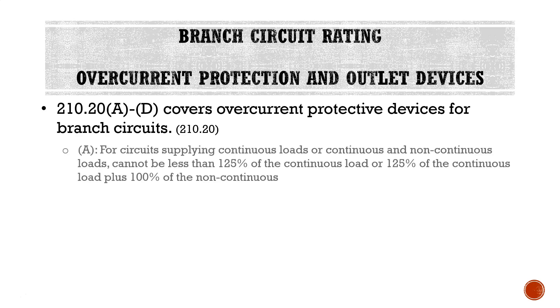Moving into Part 2 of this article, we look at overcurrent protection and outlet devices. Section 210.20A through D covers overcurrent protective devices for branch circuits. Part A is a very important and commonly used NEC rule. For circuits supplying continuous loads, or continuous and non-continuous loads, the overcurrent device cannot be less than 125% of the continuous load, or 125% of the continuous load plus 100% of the non-continuous load. A continuous load is any load that runs more than three hours at a time.